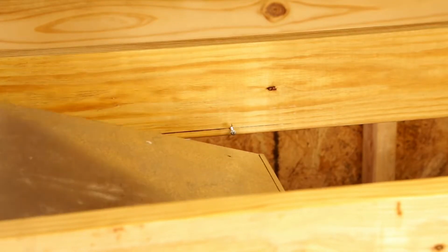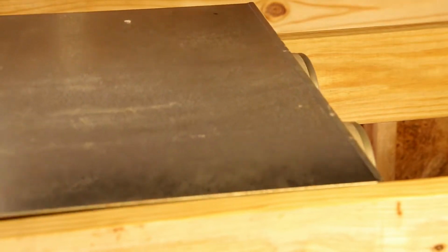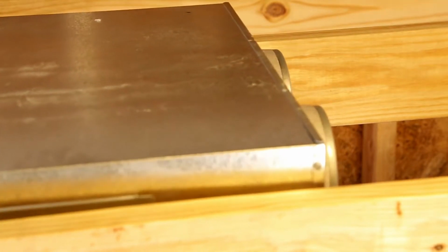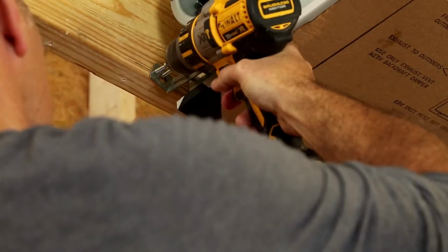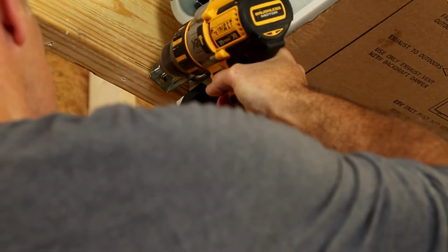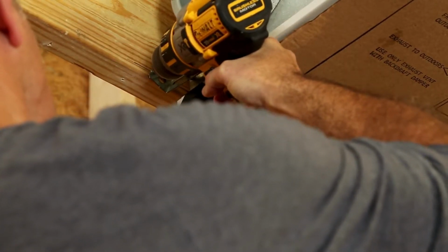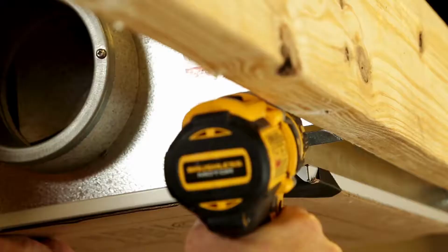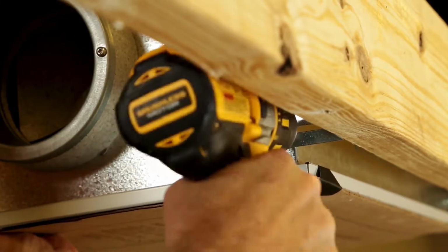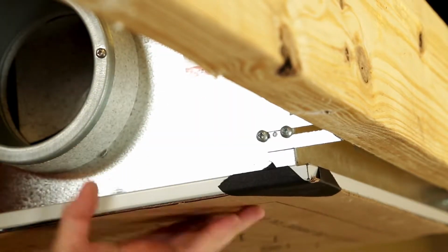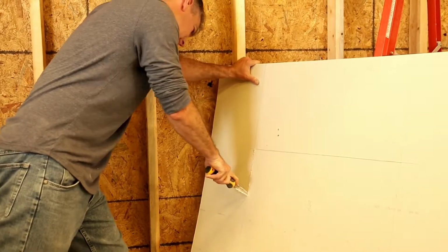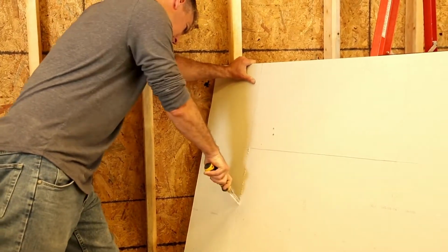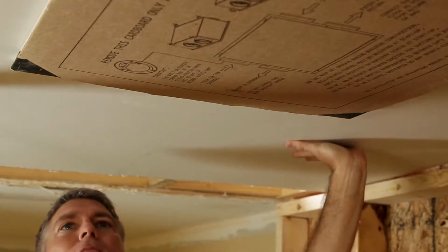Hang the lightest side of the unit on the screws mounted on the truss using the larger holes of the brackets. Secure the first brackets installed to the truss using one number 8 by 1.5 inch screw per bracket in the smaller hole of the brackets. Then tighten all screws connecting the brackets to the unit. Before installing drywall on ceiling, cut a properly sized hole in the drywall to allow the drywall to slide beneath the flange of the unit. Finish drywall normally. The access door and flange can be painted to match the ceiling color.